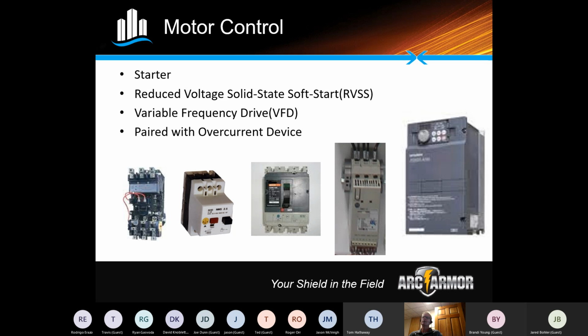This item over here is a VFD. VFDs are very practical. The cost for those has come down substantially over the years. So they're more cost effective going into panels in which you can control your motor or your pump and drive it at lower speeds, right? And be able to better fit an optimal flow condition rather than just relying on across-the-line on/off. So the VFDs definitely have their place in our industry.